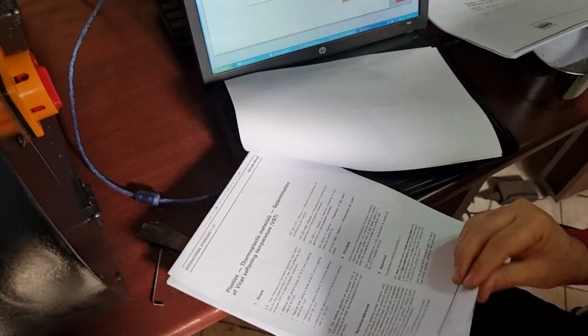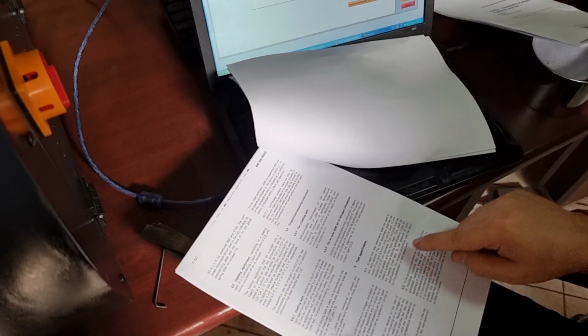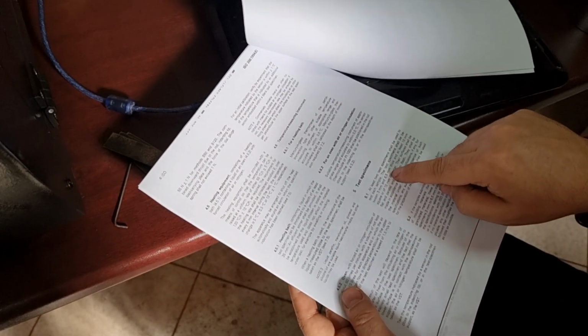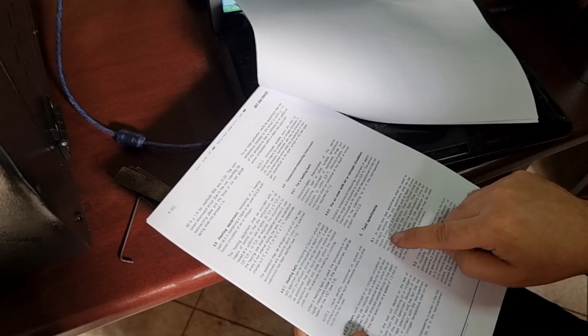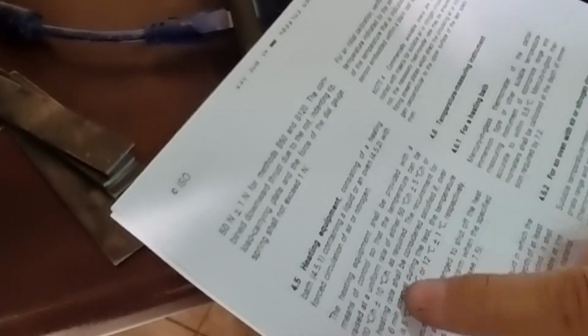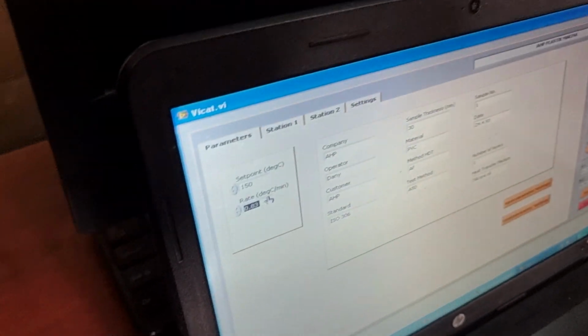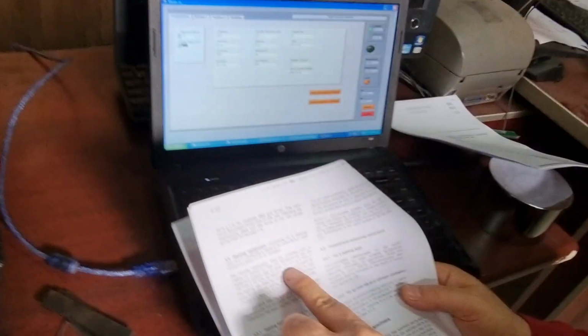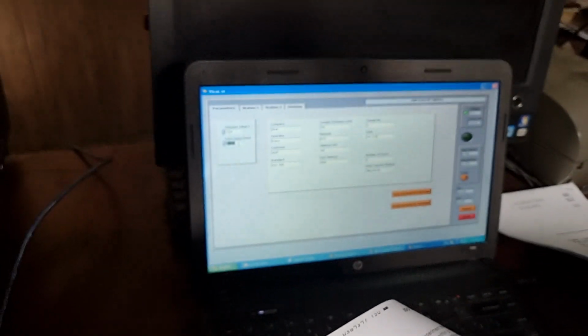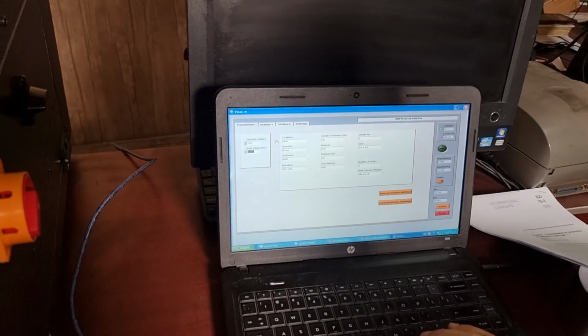You can see here the sample. The test specimen thickness needs to be 3 millimeters to 6.5 millimeters, and at least 10 by 10 square, or diameter, will be the dimensions of the sample piece for the Vicat measurement. And the heating rate, based on the method that you selected for the test, could be either 50 degrees centigrade per hour or 120 degrees centigrade per hour. That is here. For example, for this one you can select the unit of degrees Celsius per minute, and for the rate of 50 degrees centigrade per hour the value will be 0.83 degrees centigrade per minute. And after setting these parameters, you can start the test.